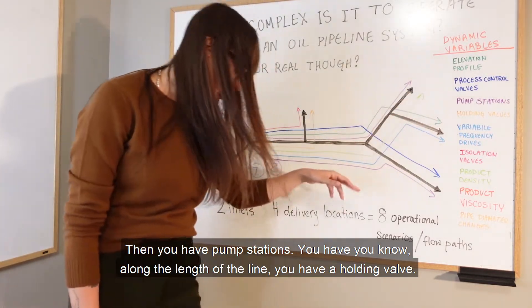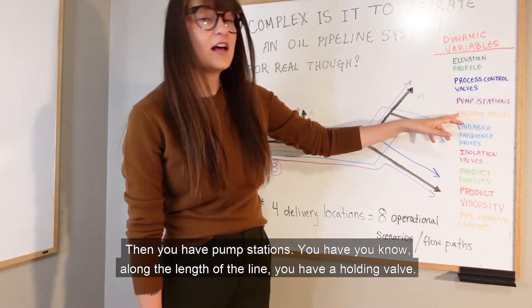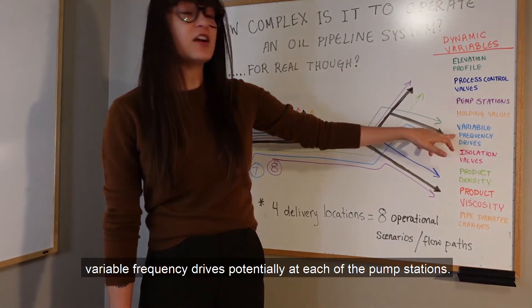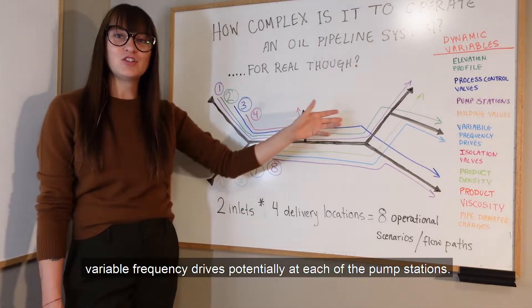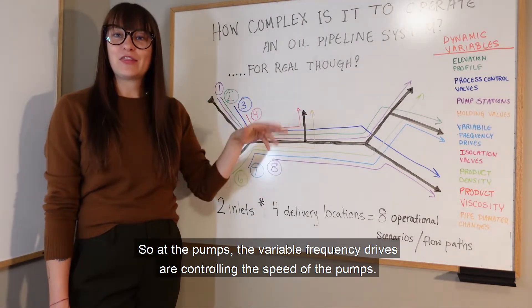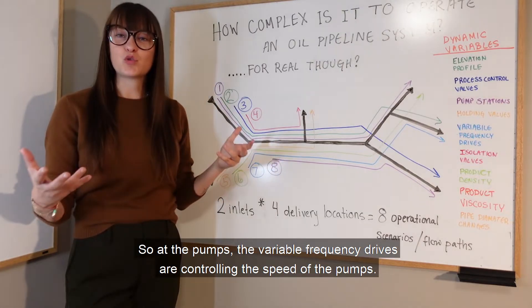Then you have pump stations along the length of line. You have holding valves at each delivery point. Then you're going to have variable frequency drives potentially at each of the pump stations. At the pumps, the variable frequency drives are controlling the speed of the pumps.